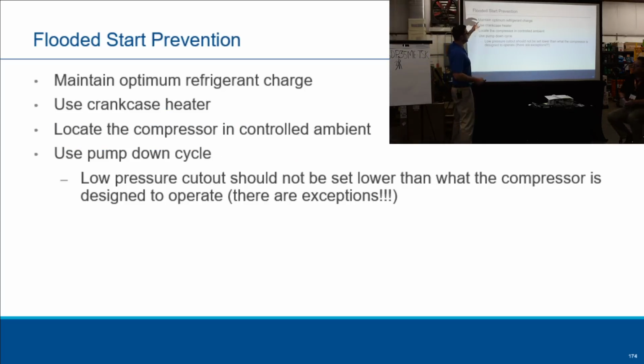Okay, maintain optimum refrigerant charge, use crankcase heater, great job. Locate compressor in controlled ambient if you can. Okay, use pump down cycle. Low pressure cutout should not be set lower than what the compressor is designed to operate.